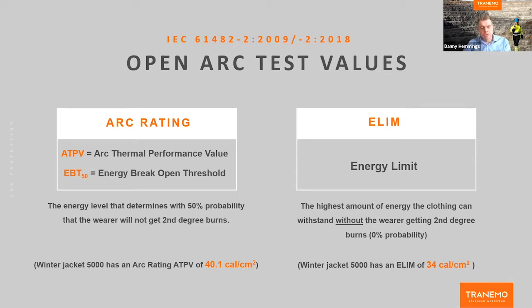So as opposed to 50% probability with the current system, where you would have what's called an ATPV, arc thermal performance value figure, or an EBT figure if the fabric itself is broken open at a particular energy level. That gives you a 50% probability. Now with ELIM, there'll be a 0% probability. And clearly what ELIM will do by virtue of that is bring down the levels of protection in calories per centimeter squared that a fabric or garment will offer.